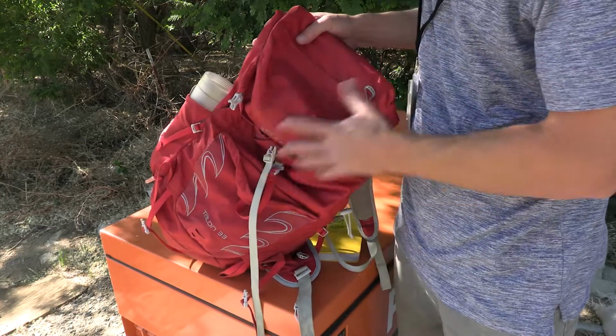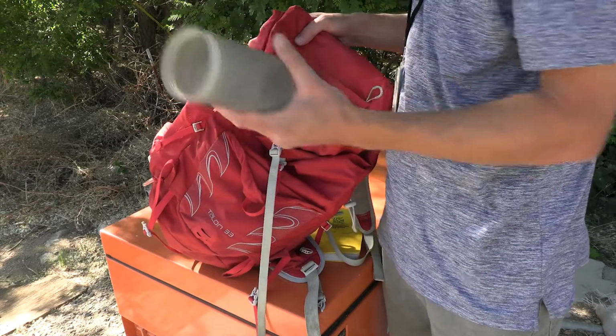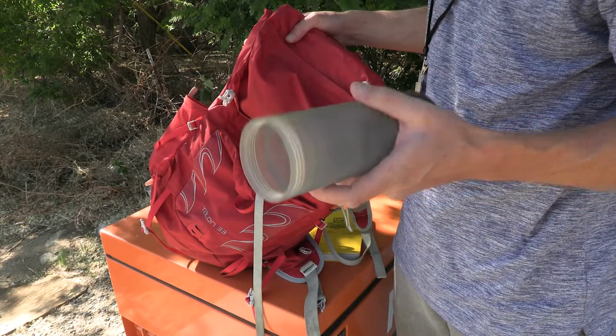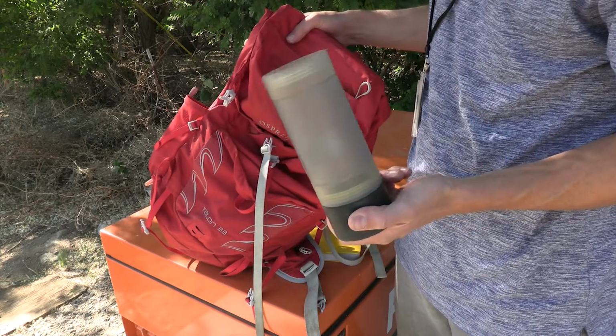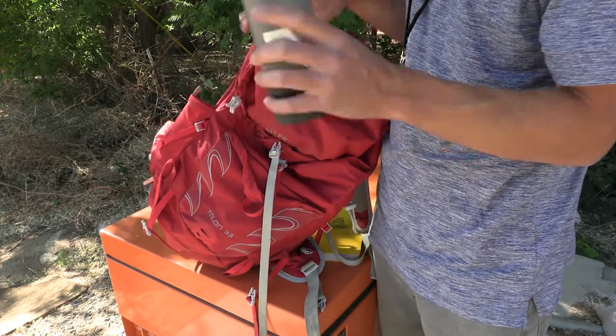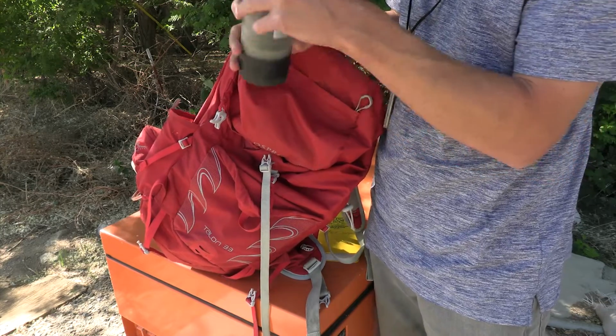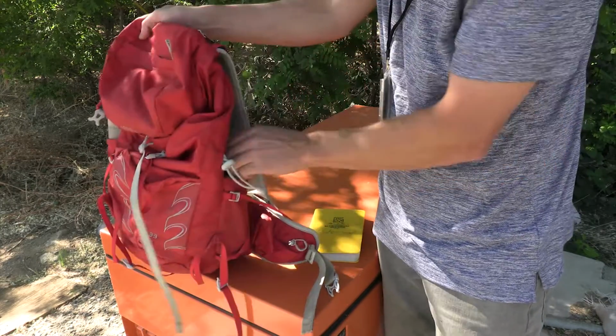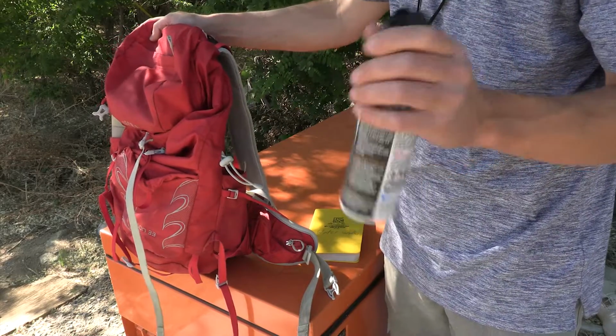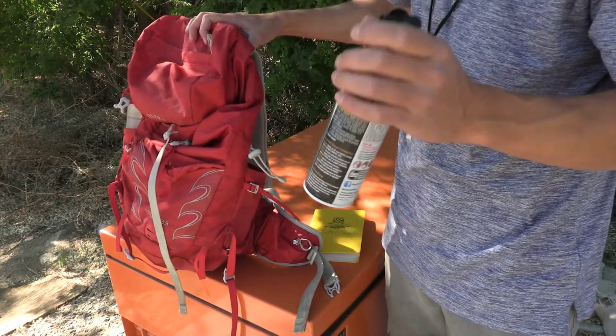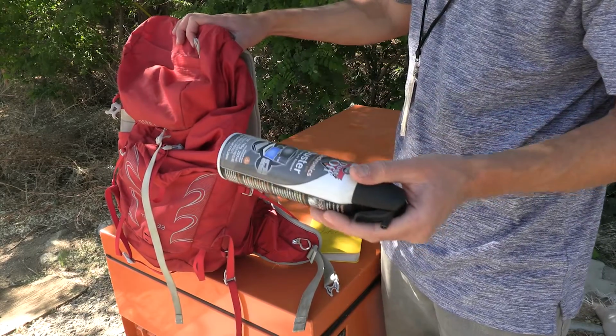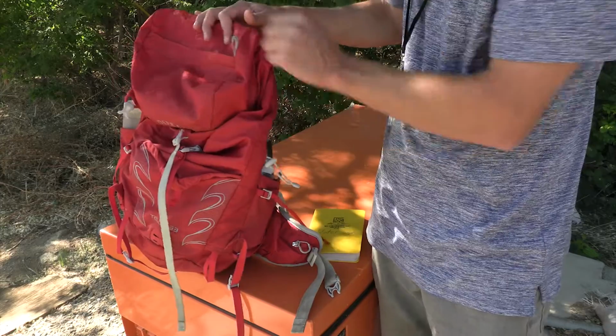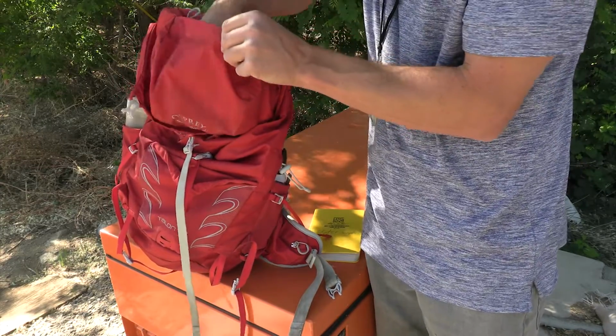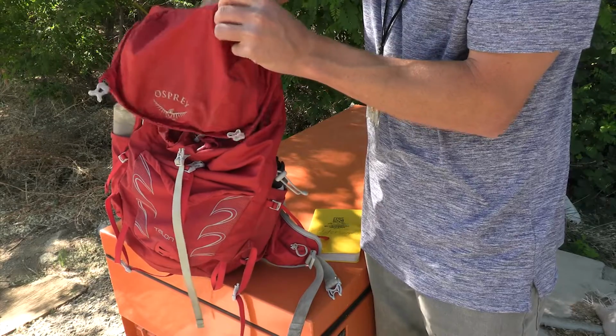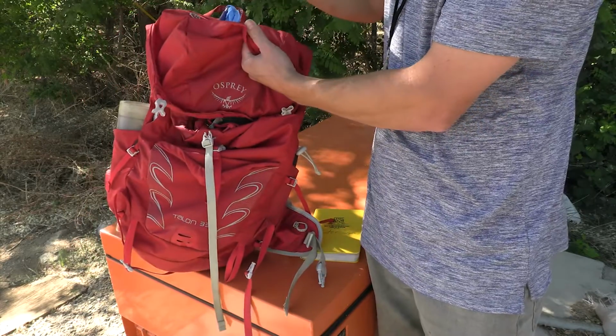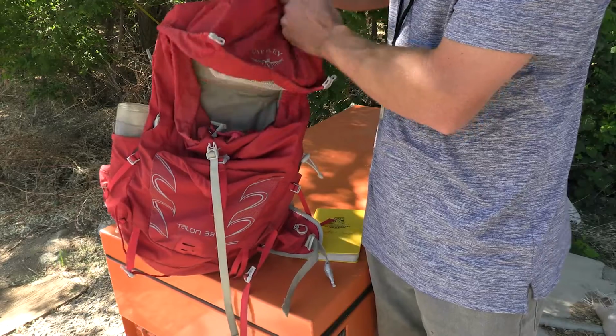What we have to start off with on the outside is our sampling cup, which covers the probes when we're traveling between sites, keeping just an inch or two of water in there. I have a can of air to clean the joints when moving the sonde between the mobile sampler and the continuously monitored system. At the top I have a bunch of gloves for water quality sampling, an extra pen, and permanent markers for E. coli or bacterial sampling.